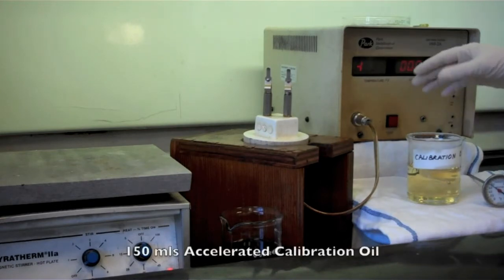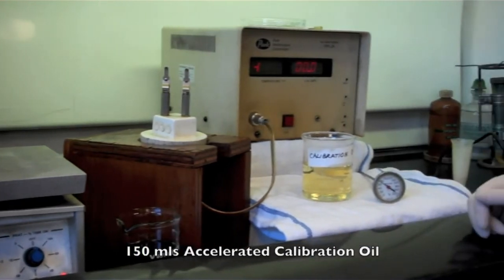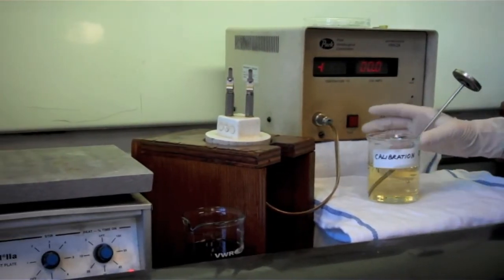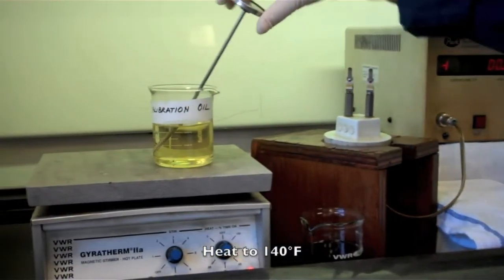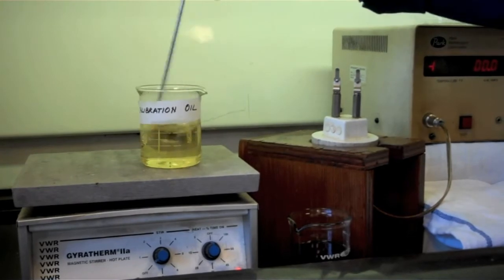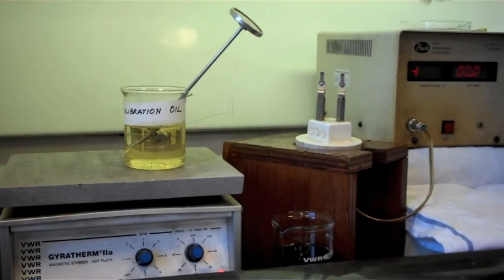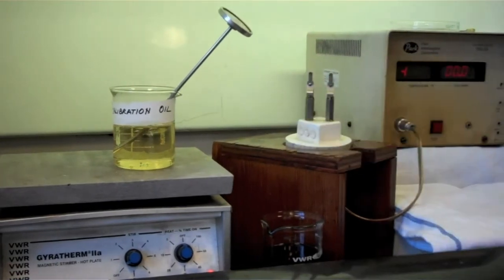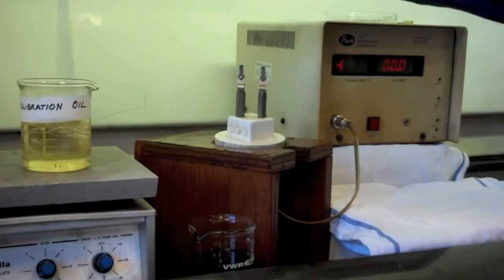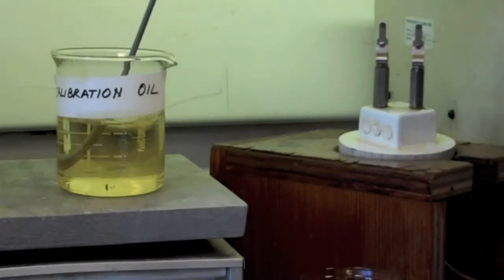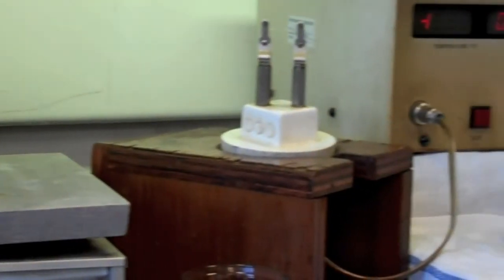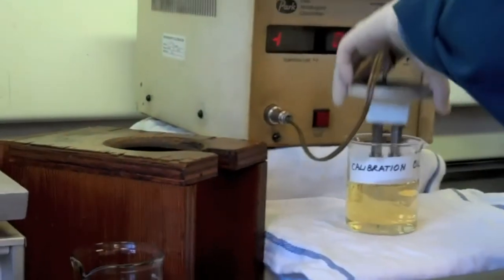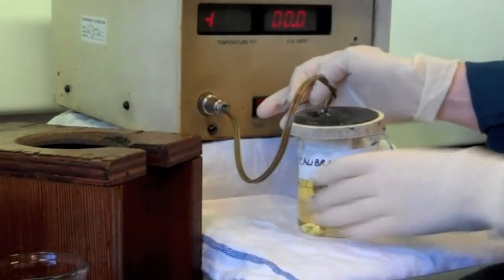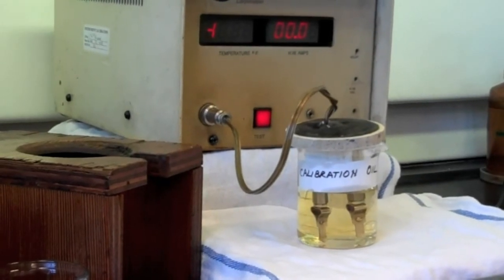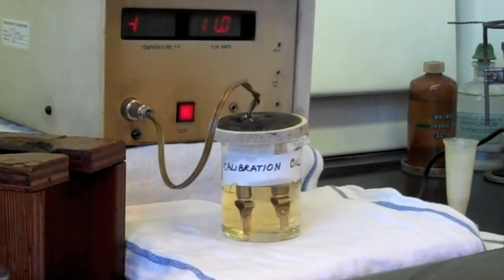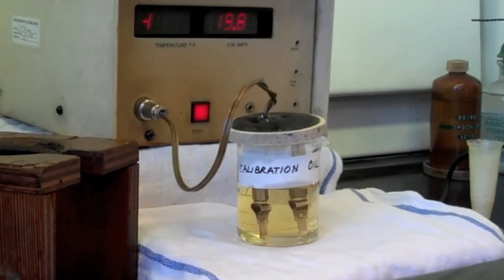How do we do it? We pour 150 ml of the accelerated calibration oil in a beaker and heat it up on the hot plate to 140 degrees Fahrenheit. Then we place the wire between the electrodes of the probe, and then put the probe in the oil. The switch of the apparatus is turned on, and as we are seeing here, the current keeps on increasing until the wire fuses.